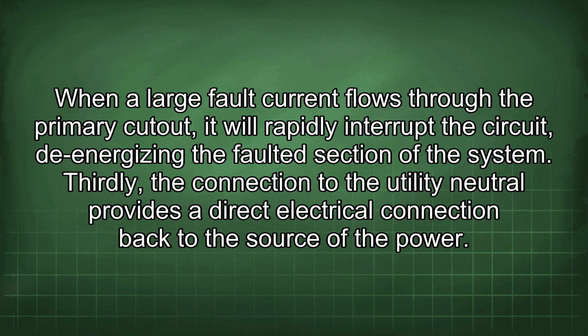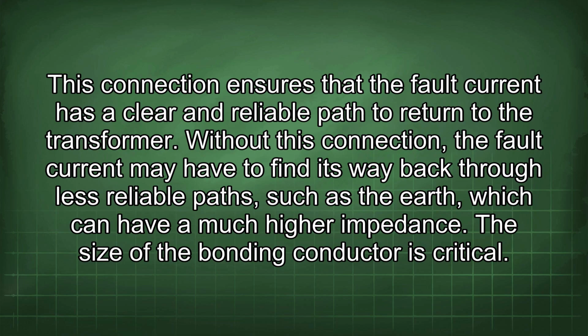Thirdly, the connection to the utility neutral provides a direct electrical connection back to the source of the power. This connection ensures that the fault current has a clear and reliable path to return to the transformer. Without this connection, the fault current may have to find its way back through less reliable paths, such as the earth, which can have a much higher impedance.